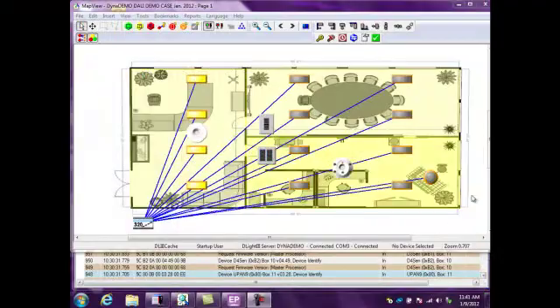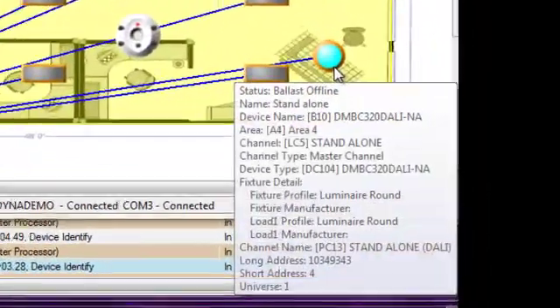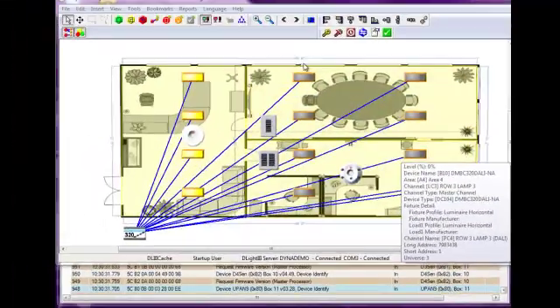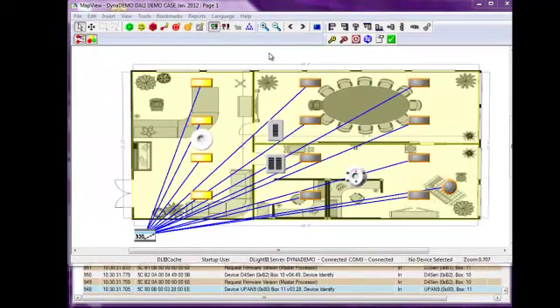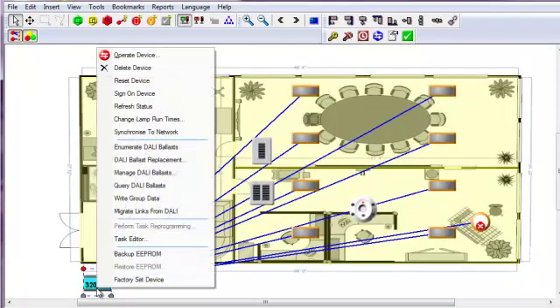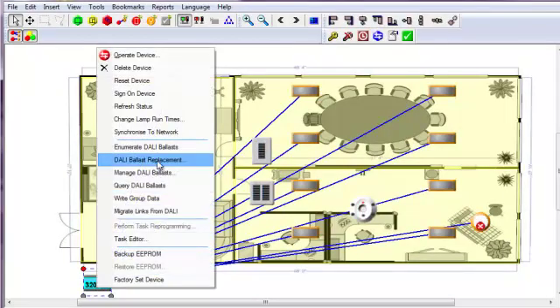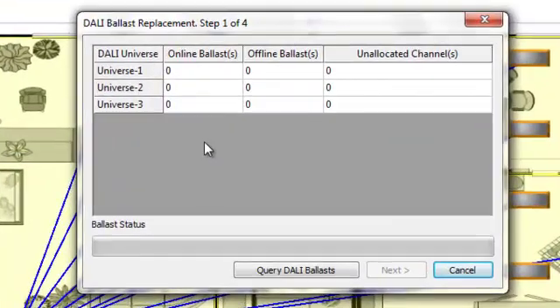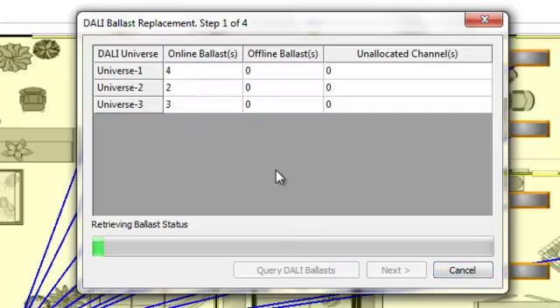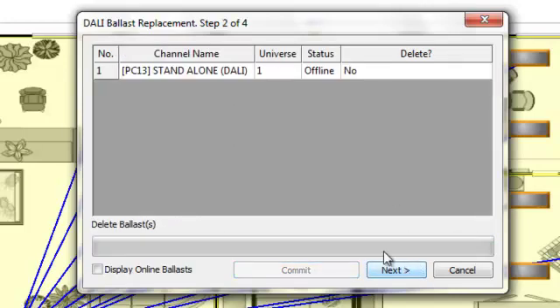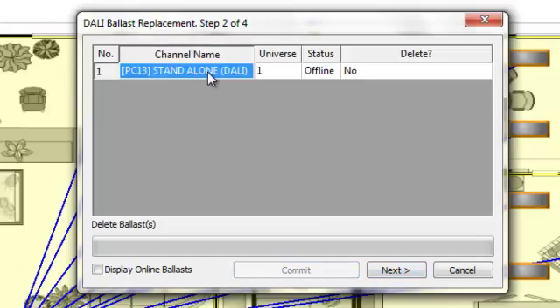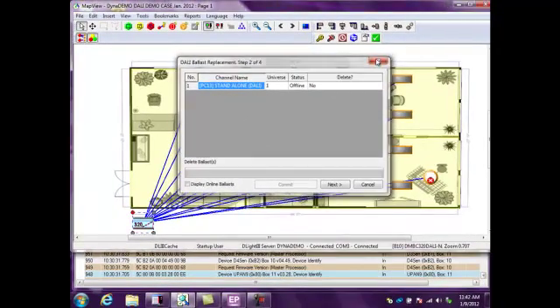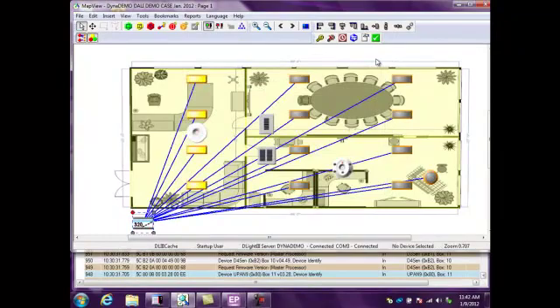Here we have a map view system. You can see we have a ballast that's gone bad. We're going to go ahead and do a DALI ballast replacement. I'm going to go up here and hit my pointer. I'm going to go down to my load controller. And I'm going to simply go to DALI ballast replacement. Here I can see my three universes of DALI. I can query my ballast. It shows me which ballasts are online. And then I do have an offline ballast here. I can simply go to next. It shows me which ballast is offline. I go to replace that. And we're done.